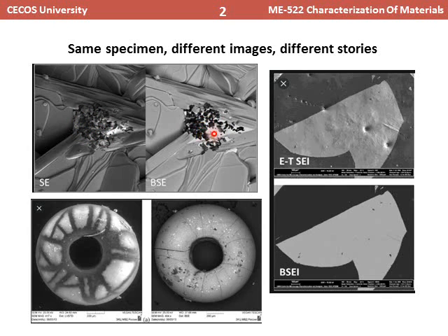So in case of backscattered electron, this lump mass can be seen as having different bodies that constitute it inside. In case of surface morphology of secondary electron, you can identify the lump mass with the base, but how this lump mass looks from the inside, you cannot see. Whereas with backscattered electron, because the penetration depth is a little bit more, you can see what's inside the surface, a little bit inside. So there are different bodies comprised inside this lump mass.